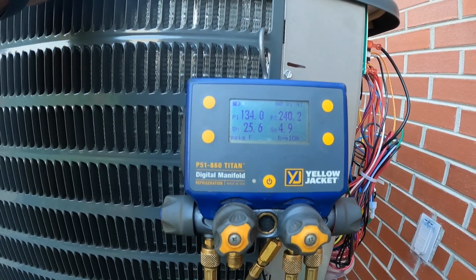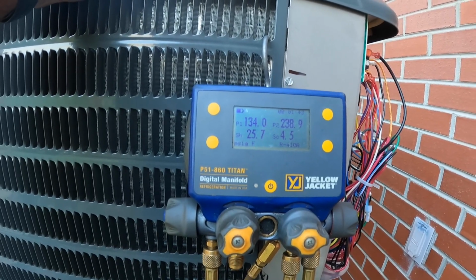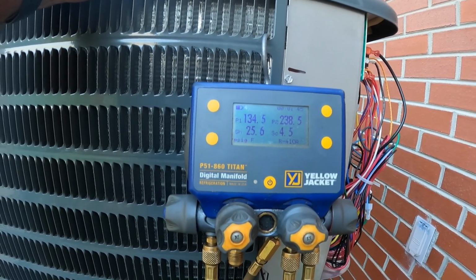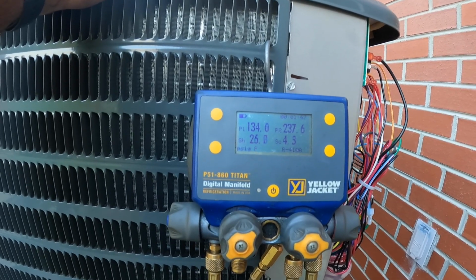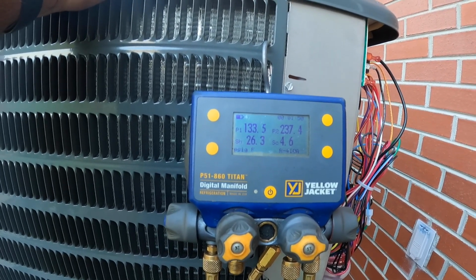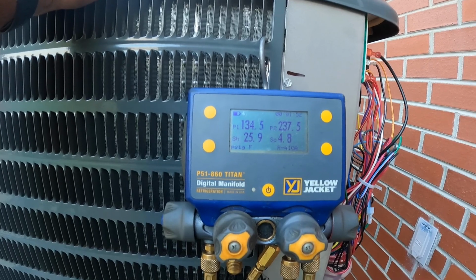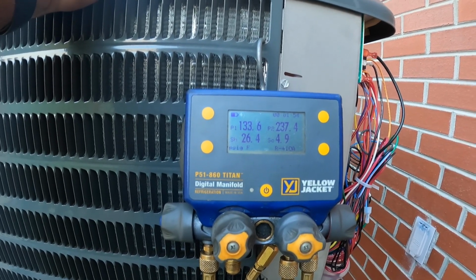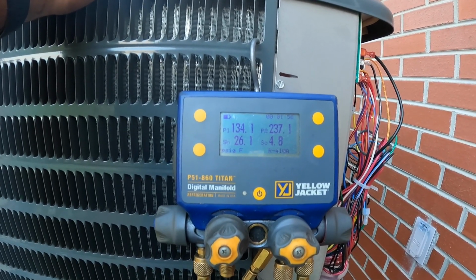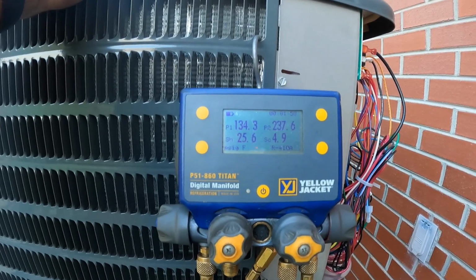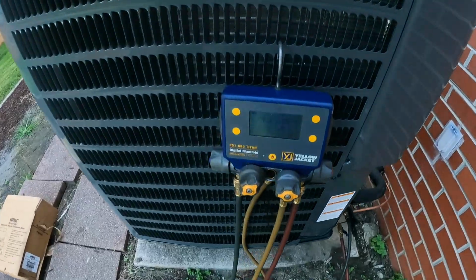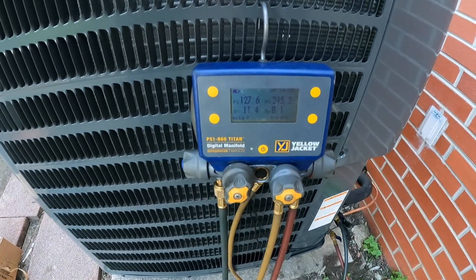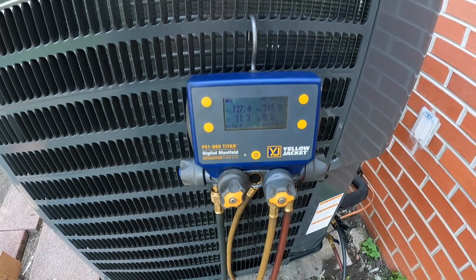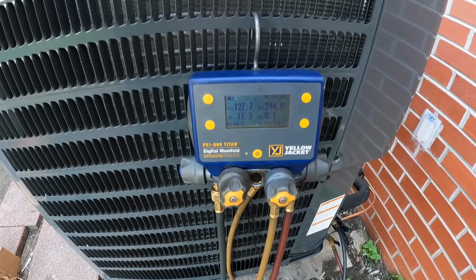Should be pretty close on charge if the factory did their job right, because we've got right at 15 to 18 foot of line set on it. So we'll let her run for a little bit here, and I'm going to start picking some stuff up. It's starting to get dark. These people can't stay out here much longer. She's running good. Got an 8-degree subcool and an 11-degree superheat.